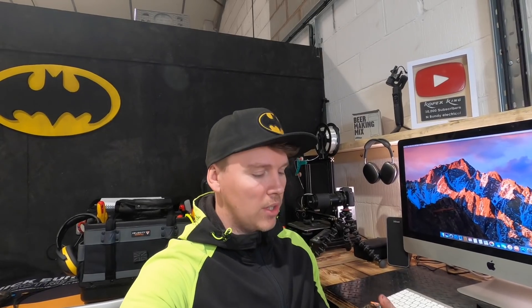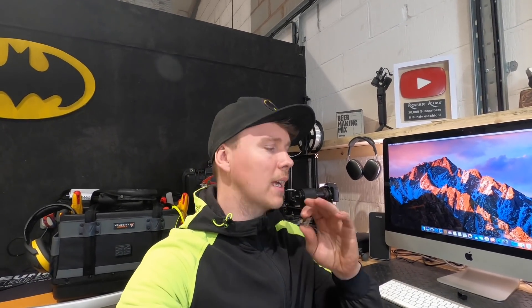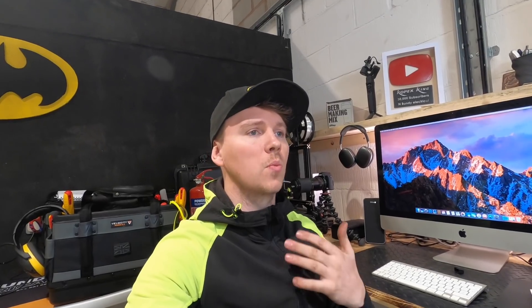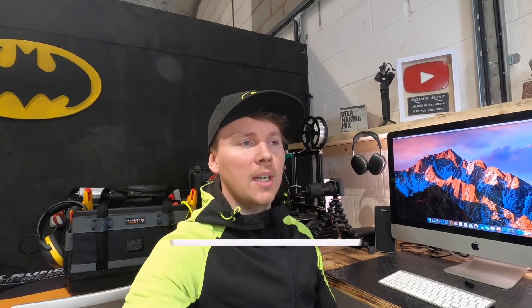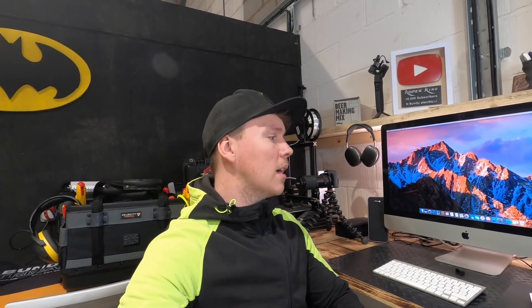I hope you found that interesting. I was quite shocked to find that the Wago actually went first. They all withstood way more than they should have — let me put that out there very clearly — they exceeded my expectations and the amperage they're rated to vastly. But it does just show the difference in what you can see on a board and what could happen versus what would happen in someone's walls, lofts, or floorboards. This is obviously worst case scenario — if someone severely puts in the wrong protective device and super overloads the circuit — but it does show that the cable lasted longer than it should have to what it says on the chart, same as the different connectors, but I think they all did fantastic. My next video should be the fire clips versus plastic clips, and see why the regulations changed and how it's affected us, and how it's useful. Thanks for watching, please subscribe, and I'll see you soon.